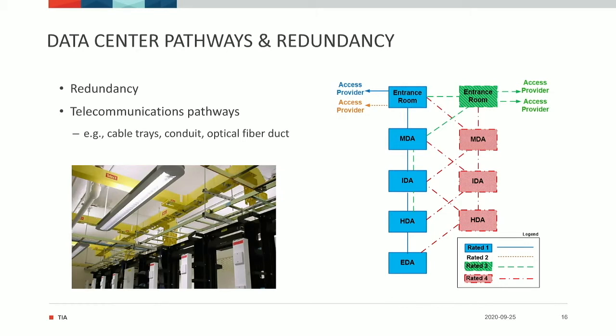You can see an example on the right-hand side of the type of redundancy that you might require. For a rated 2 data center, I would have a redundant entrance room. For a rated 3 data center, I would have redundant pathways, but only one of each of the horizontal distribution area or the main distribution area. The two routes would be redundant. For a rated 4 data center, each of the server cabinets — which we call EDAs or equipment distribution areas — would be connected to two horizontal distribution areas or HDAs, separated from each other, with diverse routing all the way to diverse MDAs.